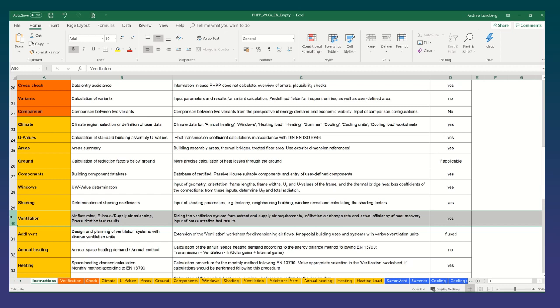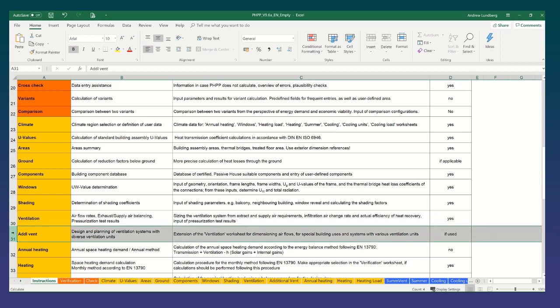And then data to do with the calculation of the ventilation system size is input for example number of occupants and the supply air requirement and then different room types and the extract air requirement. And finally there are inputs there for the exposure level of the building and exposure levels have a very significant effect on heat loss in buildings so it's important to try and obtain some level of accurate data to do with the site and its surroundings and its overall location of the building and what exposure level or zone it's at. The additional ventilation sheet then is only really used in non-domestic projects or very large domestic projects where you will have multiple ventilation units particularly where you have different ventilation units in that if you have one specific ventilation unit in a building but you have three of them then you can still use the ventilation standard sheet whereas if you have different units of different size and therefore different fan powers and different efficiencies you'll need to use the additional ventilation sheet to input multiple ventilation units.